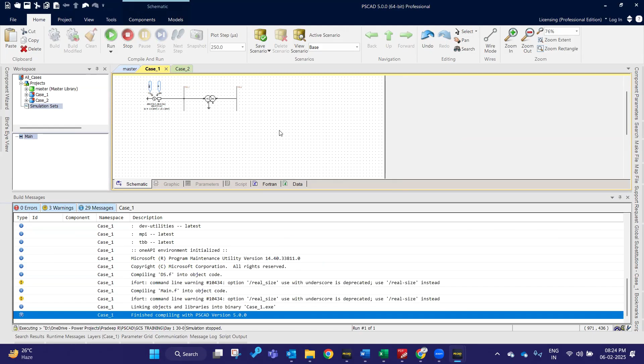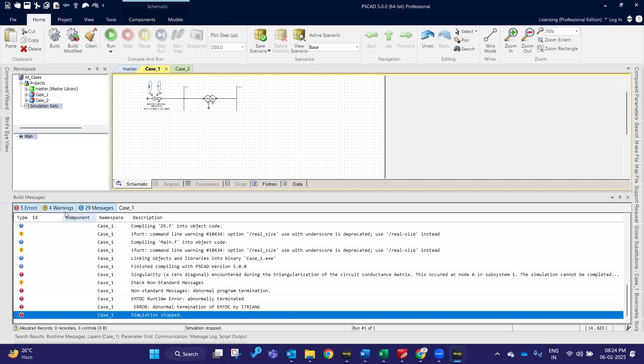EMTDC runtime error, abnormally terminated. See messages window for warnings and errors. See, now I have 29 messages, 4 warnings and 5 errors. Among them, I want to check the errors, so I'm filtering the errors. See, singularity, that is, a zero diagonal encountered during the triangularization of the circuit conductance matrix. This occurred at node 6 in subsystem 1. The simulation cannot be completed due to numerically ill-conditioned matrices. So it is showing a general error.